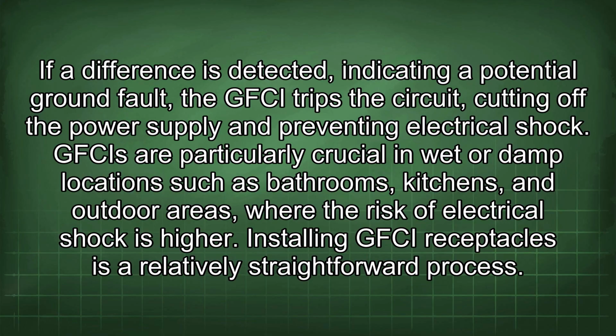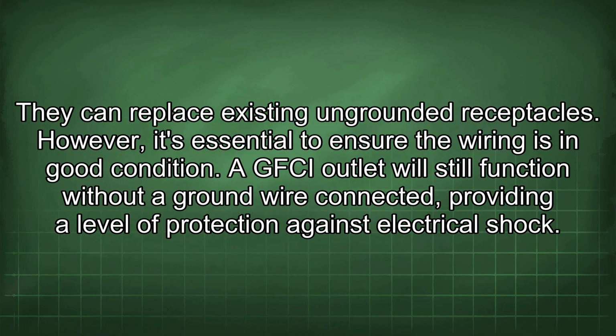Installing GFCI receptacles is a relatively straightforward process. They can replace existing ungrounded receptacles. However, it's essential to ensure the wiring is in good condition. A GFCI outlet will still function without a ground wire connected, providing a level of protection against electrical shock.